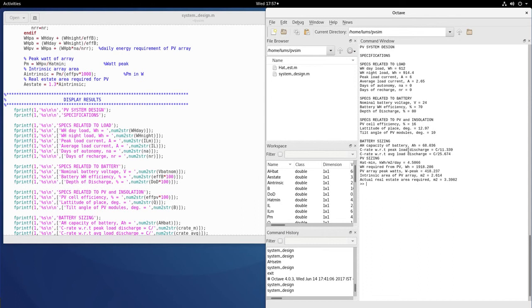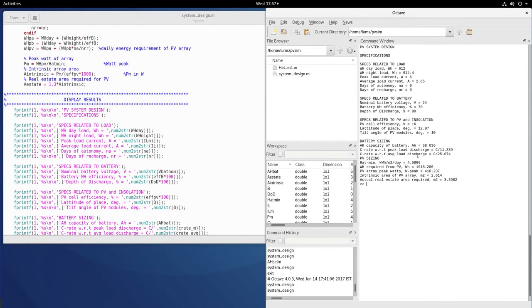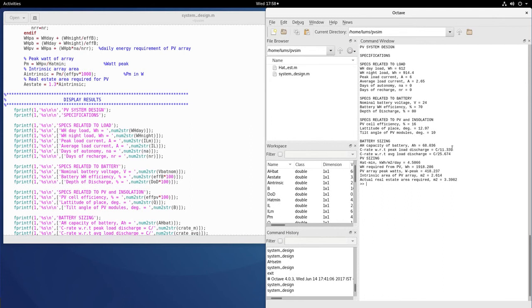The battery sizing shows an ampere-hour capacity of 68 Ah. The C-rate with respect to peak load discharge and average load discharge is calculated by dividing ampere-hours by peak current and average current. For C/11, you can use the nearest tens value like C/10 or C/20, as discussed in manual calculations.